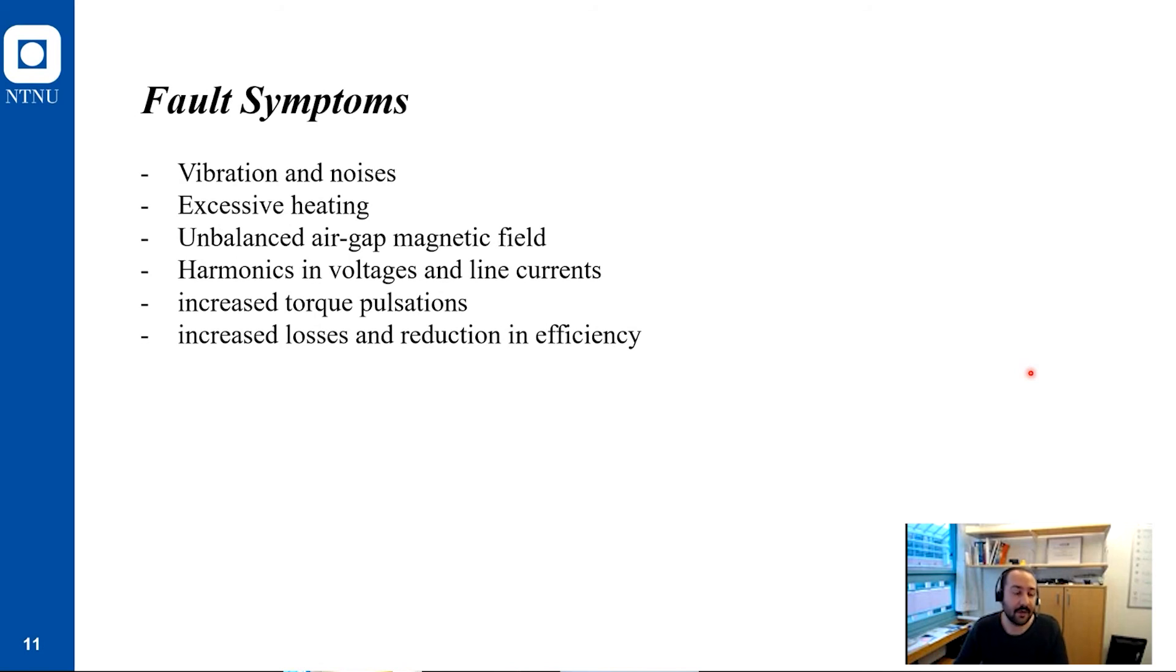What is the symptom or consequence of these faults? The first one is vibration and noise. When we have a fault it can insanely increase. Excessive heating, unbalanced air gap magnetic fields, or having a different level of harmonics in the voltage or line current is also a symptom of fault. A fault also could result in torque pulsation or efficiency reduction as I mentioned.